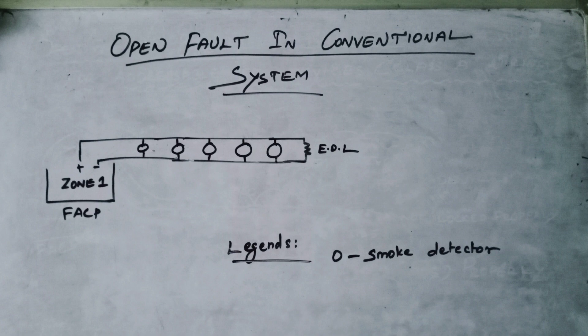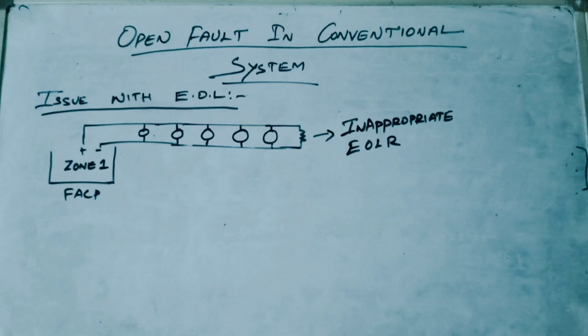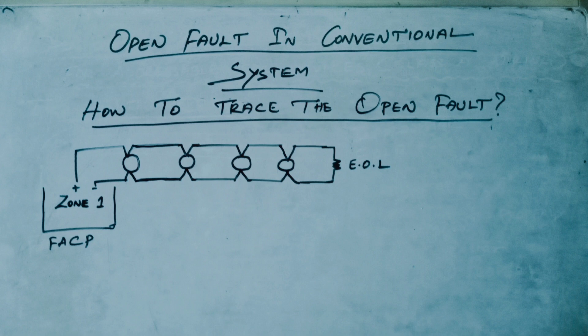I am now figuring out the open trouble in a conventional system. I'm using a typical conventional design with initiating devices like smoke detectors and pull stations. For panels that use a 4.7 kilo-ohm end-of-line resistor, check and make sure the end-of-line resistor is 4.7 kilo-ohms. You can find the end-of-line location by referencing the drawing. Doing this first makes troubleshooting much easier.